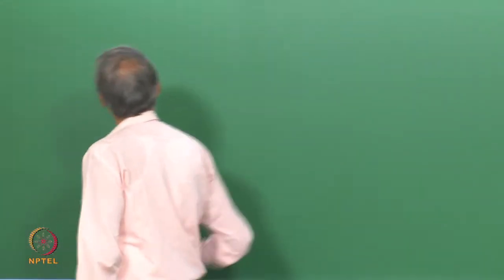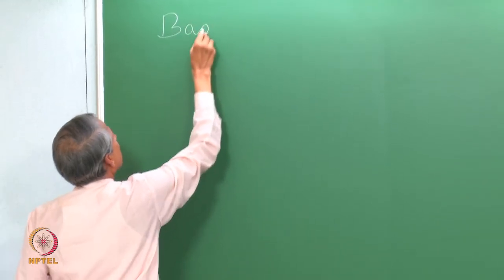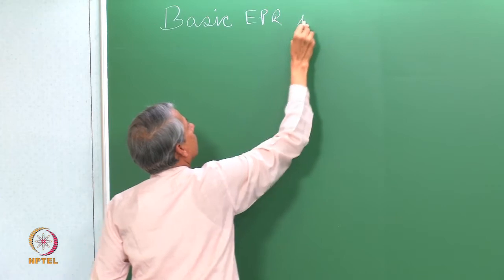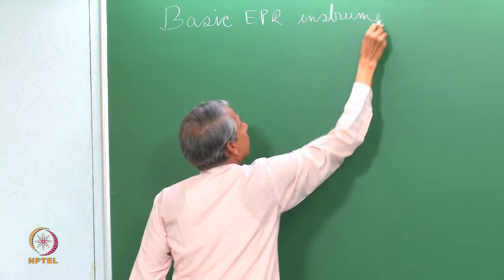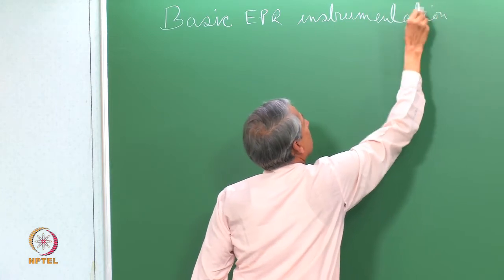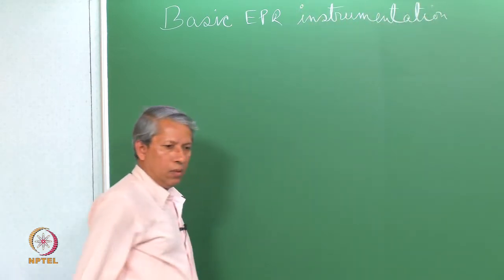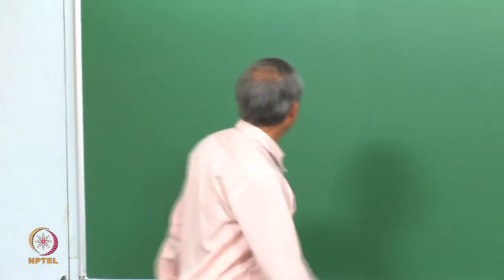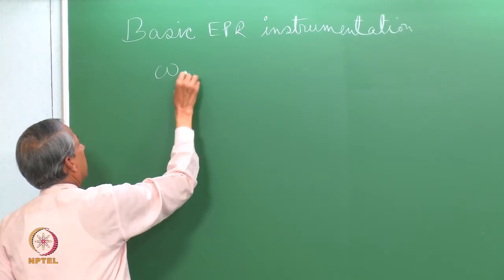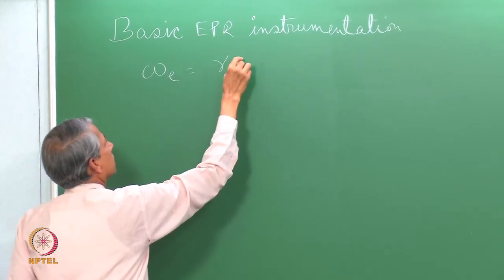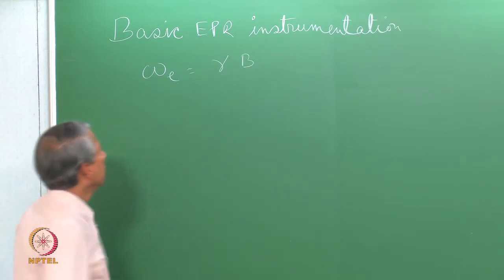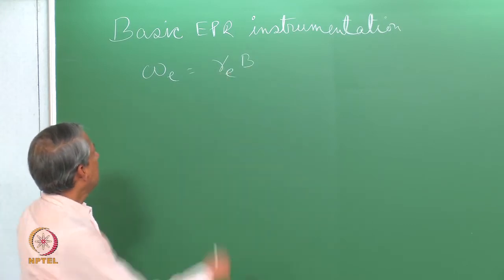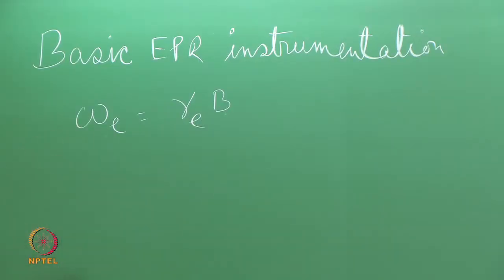Today we are going to discuss the basic EPR instrumentation — the items used to make an EPR spectrometer. We have seen in the earlier lecture that the Larmor frequency of an electron is given by the gyromagnetic ratio of the electron, the magnetic field, and the frequency of precession.